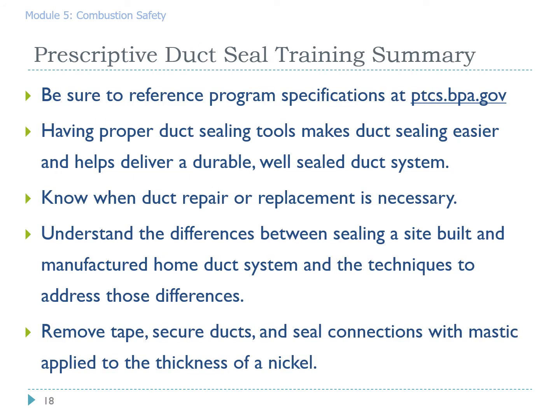To summarize all 5 modules and hit the high points, we want to make sure that you know where all relevant program specifications live. They live at ptcs.bpa.gov. Hopefully you'll have proper duct sealing tools. This makes your job easier and helps to deliver durable, well-sealed duct systems. Hopefully we've given you enough to think about when duct repair or duct replacement is necessary as compared to just trying to seal it. We hope you understand the differences in sealing between a site-built house and a manufactured home and the techniques to address those differences. Once again, we want to repeat that you have to make a good faith effort to remove any existing tape. You must secure ducts with mechanical fasteners and seal connections with mastic applied to the thickness of a nickel.